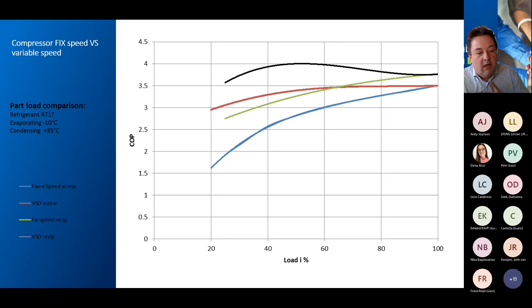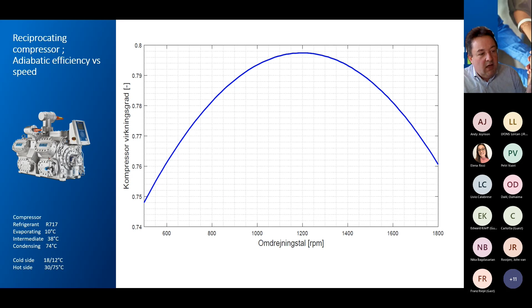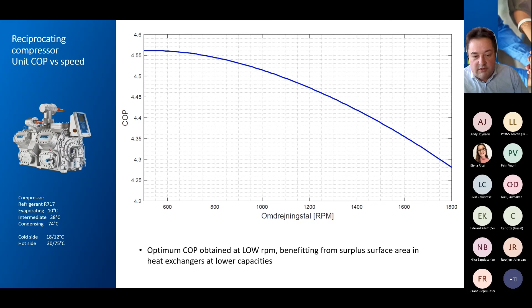Second thing is that a heat pump or a compressor also has a change in adiabatic efficiency. And lastly, when you put this all together, as you lower the capacity on a machine, you actually increase the relative size of your heat exchanger. That means over the capacity range, in this case from 500 to 1800, there is an increasing COP due to the overcapacity on heat exchangers and lower delta pressures in the compressor. That gives an increasing COP as you move towards the lowest capacity, and that was also achieved in this project. So I think I have used all my time, or maybe more.